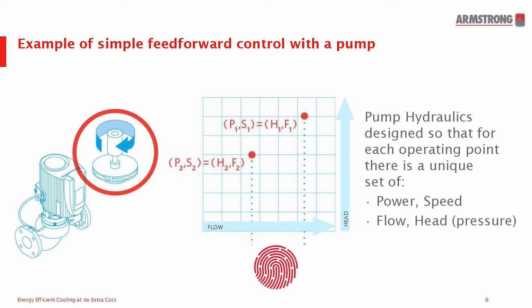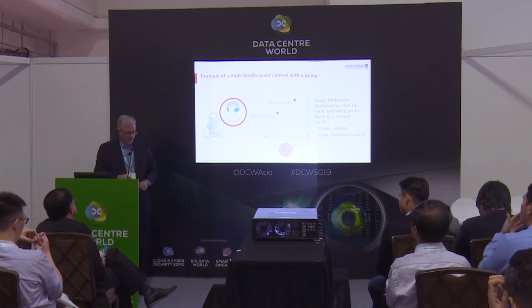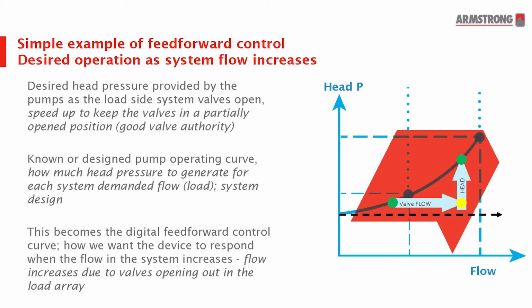We call that head and flow for these two dimensions, a unique combination of head, flow, pump power and speed. So with an intelligent pump where we have the power supply coming into the pump and it has its power converter, its frequency converter, its motor, and all that gets mapped in the factory, when we are operating the pump at a certain power and speed, we also know the head and flow. So now we've created essentially a flow meter out of our pump or a pressure sensor out of our pump because it has that intelligence through that mapping.